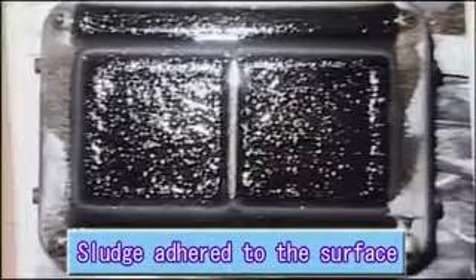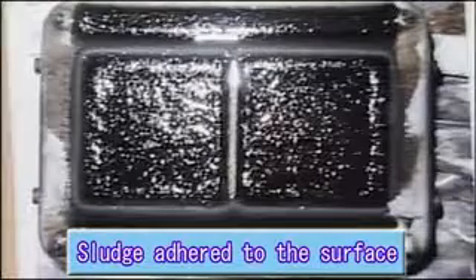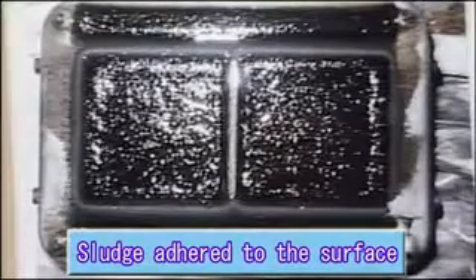This shows sludge adhering to the surface of the microseparator. If we zoom in on the sludge separated from the oil, we can see that it has a sticky, tacky nature.